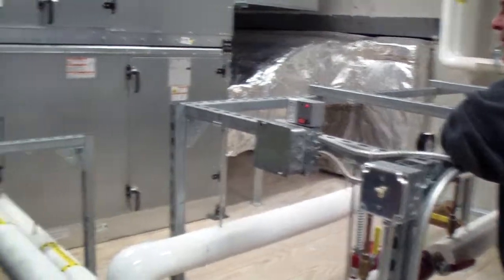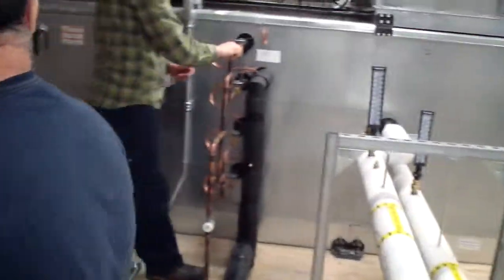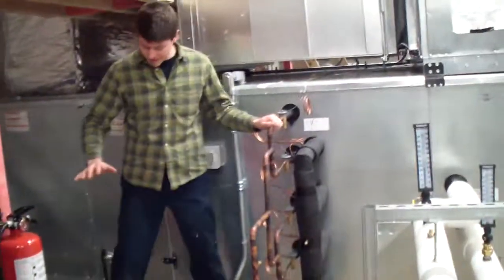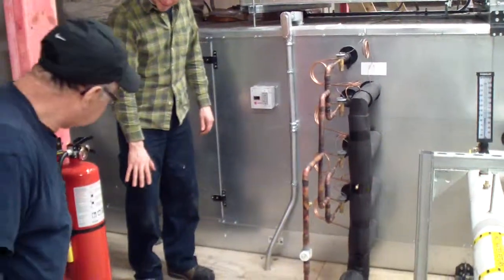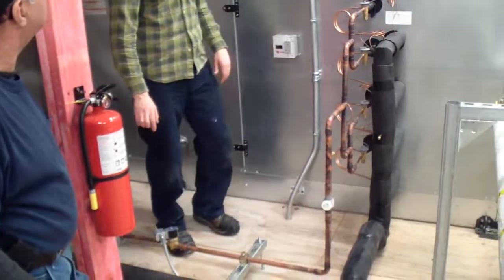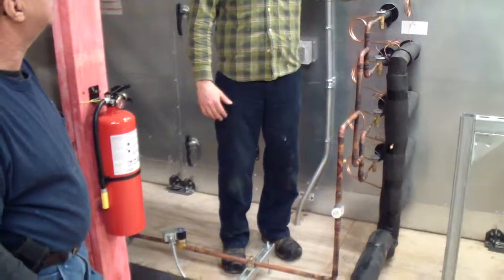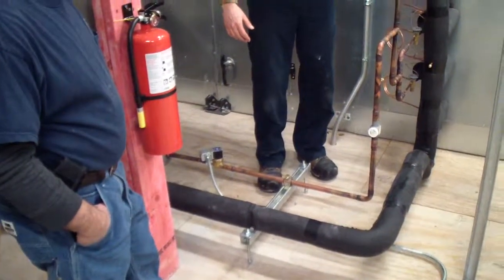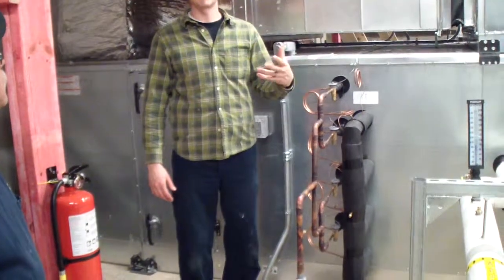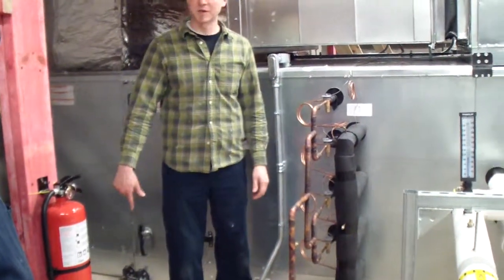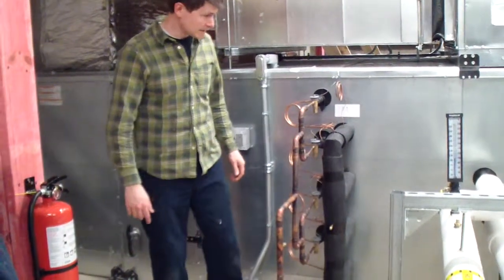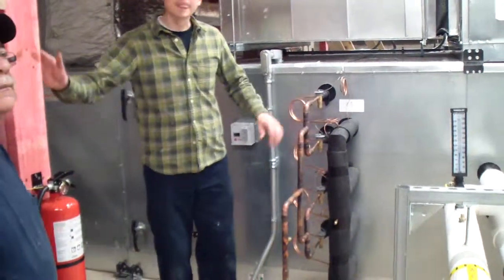And then you've got your bypass that just allows it to circulate water through for freeze protection. And then this is your chill water coil. Your DX coil hasn't been started up yet, but here's your solenoid. The command for this comes from outside the unit, so we send an enable through software to the unit itself, and then that decides when it needs to come on and off, and that's what cycles the solenoid. So the brains is the outdoor unit?